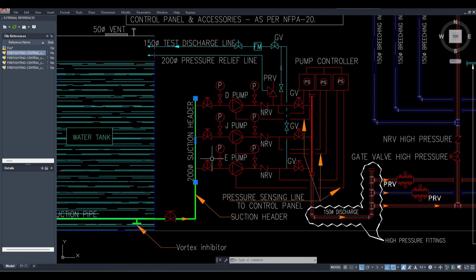So strainer will not be there, just isolation valve. Actually if you want to keep it you can, but that strainer is very different - a basket strainer type, a big strainer you have to keep, and it takes space. The codes don't say to use it or not use it, so that's why people don't use it here. But in domestic it is a must, because domestic water is for regular use, whereas this water is for suppressing fire, so cleanliness of the water is not as compulsory as domestic water. You have to understand that.